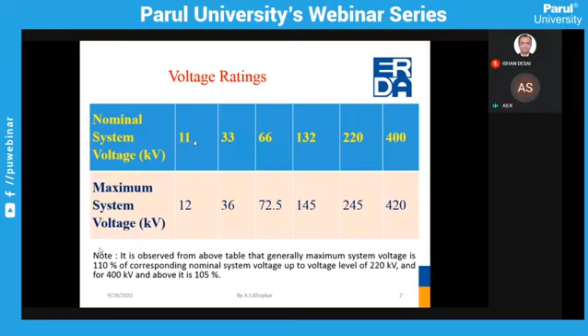Because if we keep the same ratio here also, then the insulation system of 400 kV we should design for 440, and the gap of 20 kV looks marginal. But when we design the 400 kV power transformer having a maximum system voltage of 420, versus a power transformer having a maximum system voltage of 440, then the cost of the transformer may be more than 50% higher than the original cost. And this is why, from the economy point of view, from 400 kV onwards, the nominal system voltage and maximum system voltage differ by only 5%.